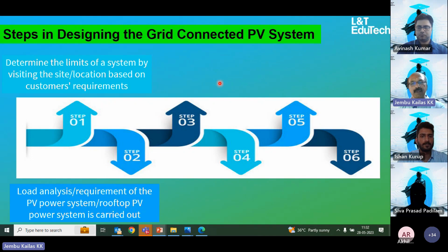Then you have to do the load analysis. You should say what the load pattern is, and what the load constitutes actually. So every piece of information, and what is going to be your demand, you have to calculate. What is going to be the maximum demand of the load in a day, that you have to calculate. That is going to be your input. Then you have to design the solar PV array based on the load requirement and also based on the radiation level of that area. So every aspect you have to consider. The radiation level you have to calculate, and also what the power requirement is. Both you have to take into consideration, and you have to calculate the PV array. There are different calculations available, and we have a lot of software also available.